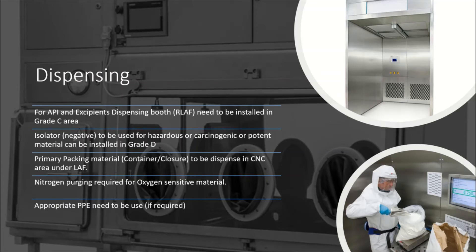The next major step is dispensing, where we ensure all raw materials, API, solvents, and whatever is required for manufacturing are dispensed. Dispensing areas are installed and maintained as Grade C. We perform dispensing under laminar air flow (LAF). There is also the option of doing dispensing of raw material and API under isolators — negative isolators are majorly used for hazardous, cancerous, or potent materials. Isolators can be installed in Grade D or Grade C areas.